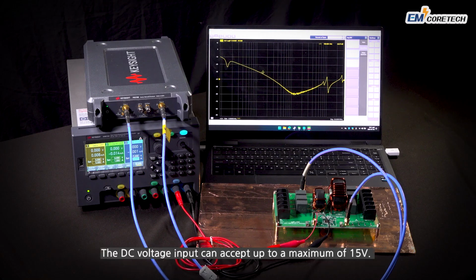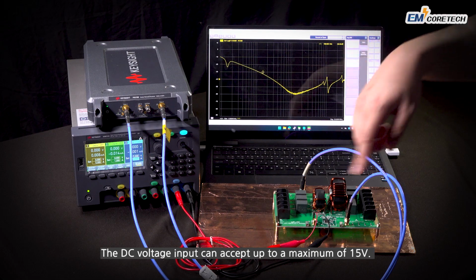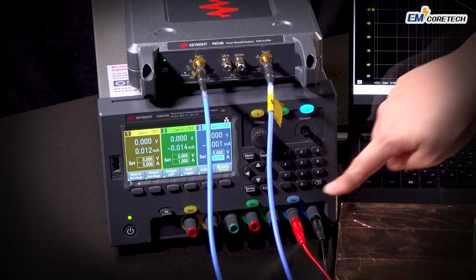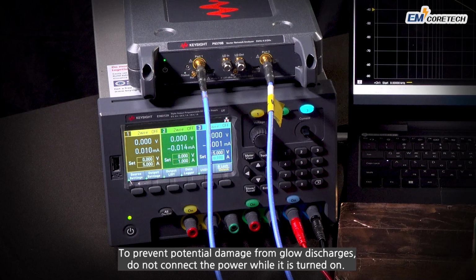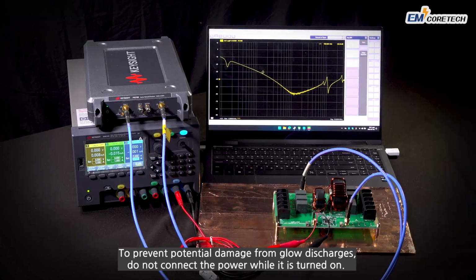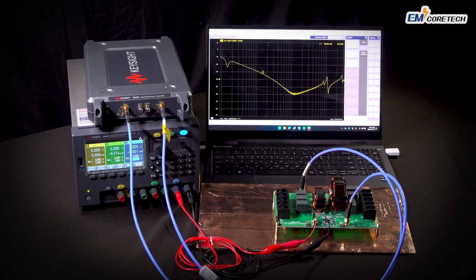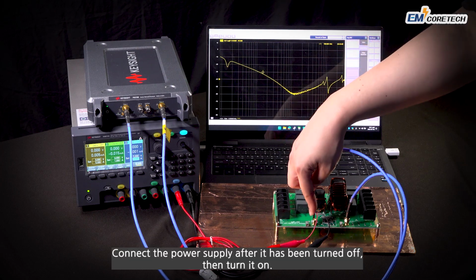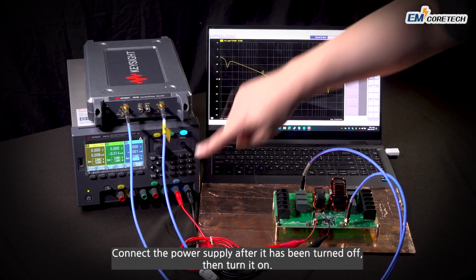The DC voltage input can accept up to a maximum of 15 volts. To prevent potential damage from glow discharges, do not connect the power while it is turned on. Connect the power supply after it has been turned off, then turn it on.